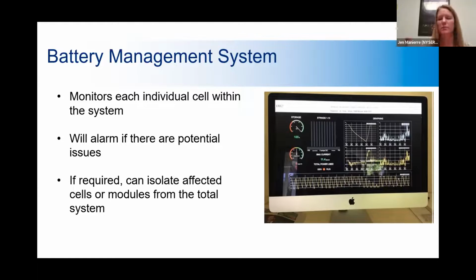And if something does go wrong, maybe one of those little cells overheats, it can flag that, send off an alarm, or shut down and isolate that specific cell. Or if it's a whole module that's been affected, shut that down and isolate it until the problem either is fixed, or if not, you can remove that part of it and do some maintenance and replace it with cells that are functioning properly. So this is the eyes, the ears, the brains of the energy storage system. And even at the residential level all the way up through utility, they're all going to have this, monitoring the system to make sure it's working, setting an alarm if it is not working properly, and also even taking action to correct any problems on its own, even without human interference in some cases.